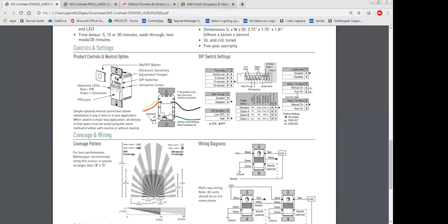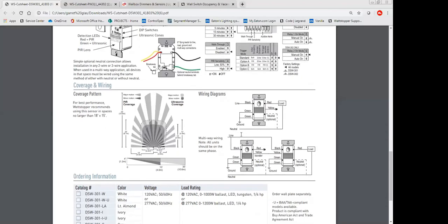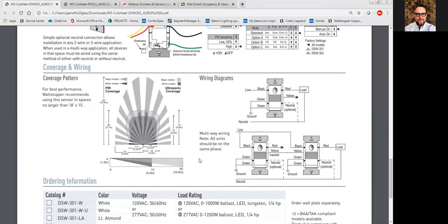It's a common thing that we'll get a phone call every now and then where someone will say, hey, my motion sensor is defective, it doesn't automatically turn the lights on. Easy to troubleshoot, right? Hey, Garrett, one thing, correct me if I'm wrong, but the state of Illinois has adopted energy code IECC 2018, so I believe they have to have vacancy instead of occupancy as well. Correct. In the majority of spaces, there are some exceptions for corridors and public lobbies, but private offices, conference rooms, all that stuff does have to be vacancy.